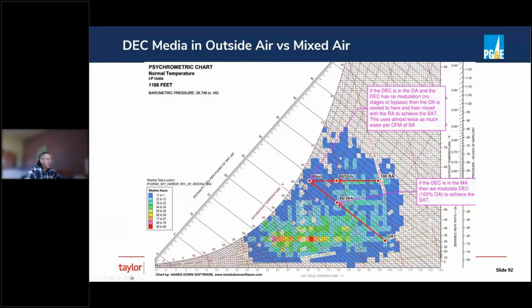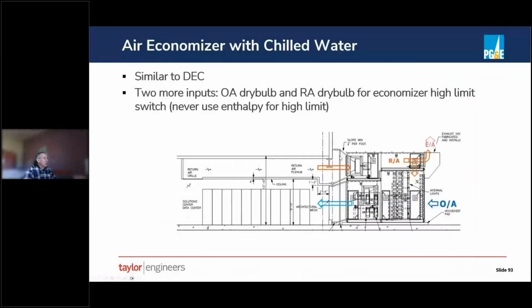And suffice it to say, you can put it in either location, but putting it in the outside air uses more water. Okay, so we've talked about air economizing with direct evap, very similar concept with chill water. One difference is that now you do care about outside air conditions because you're typically going to have an economizer high limit switch that you're going to use to switch from free cooling to full mechanical, or from partial, integrated free cooling to full mechanical.